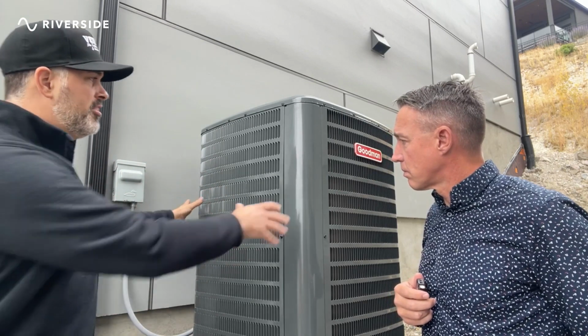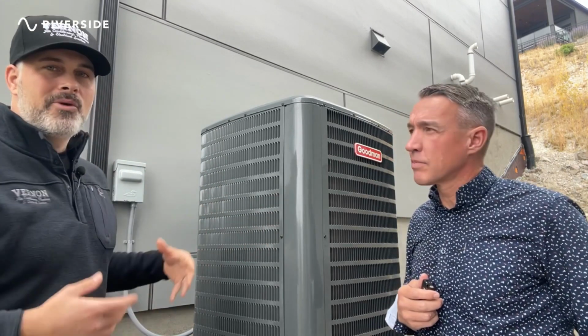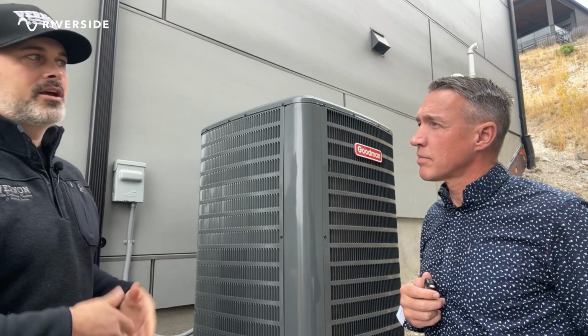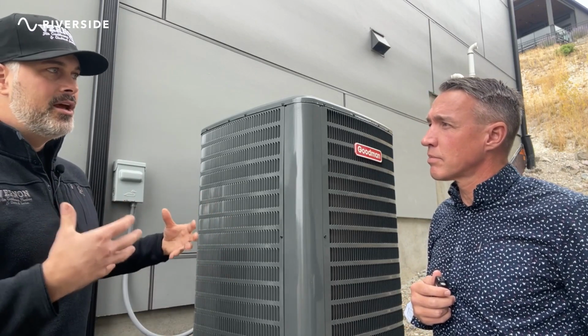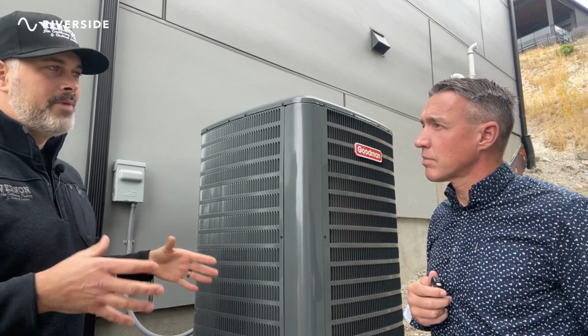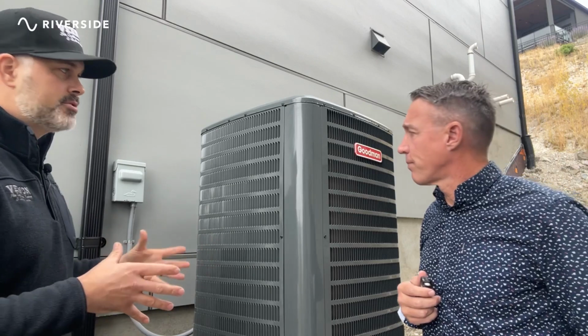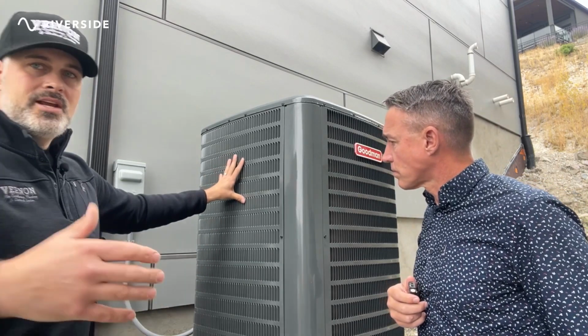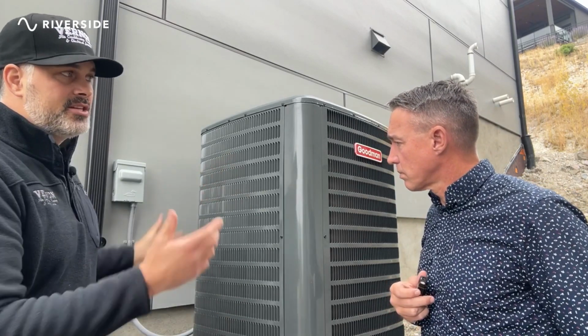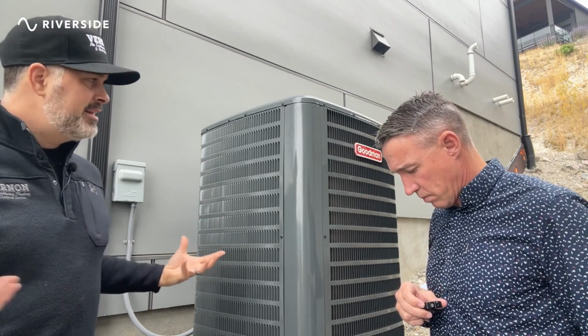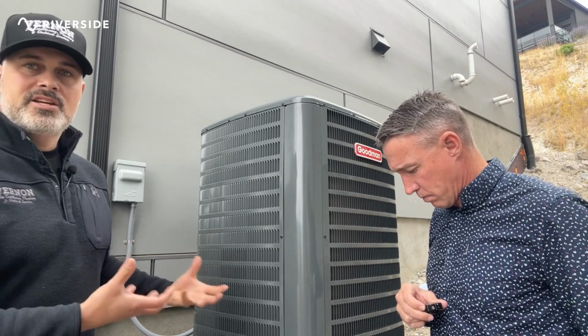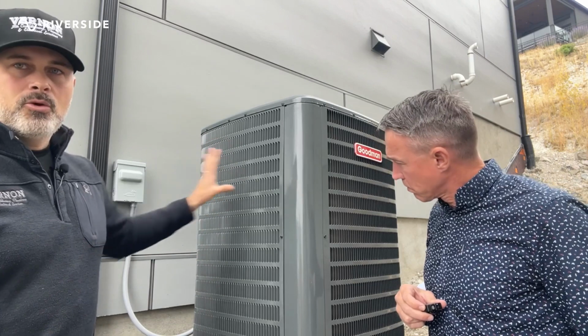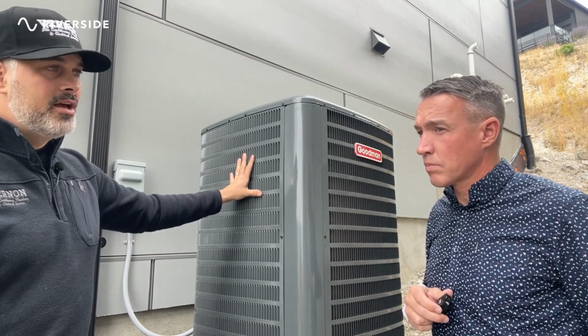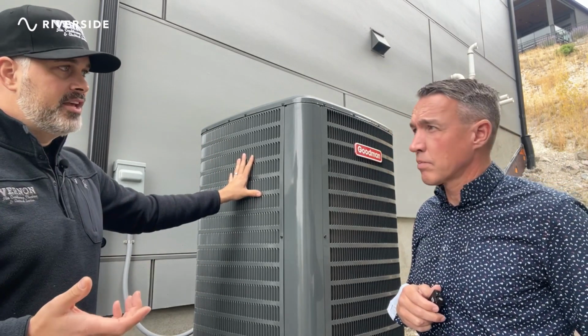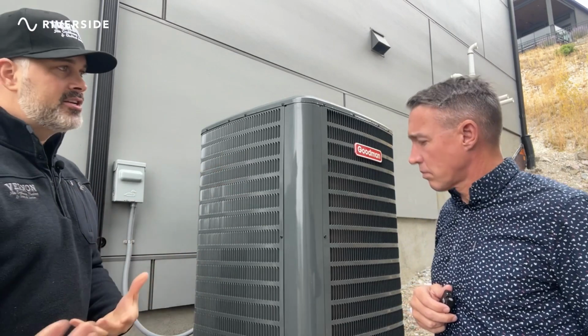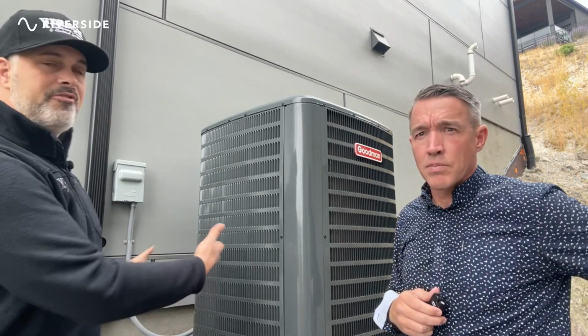In heat pump mode, this absorbs heat, which sounds a little bit crazy. It could be minus 30, it's still absorbing heat. You can actually absorb heat down to about minus 460 degrees. That's absolute zero. But this absorbs heat, and then it travels back in near the furnace to discharge it. Now, from a maintenance standpoint, this is a heat exchanger. So if we can't get airflow across this because it's dirty, it's not going to absorb or get rid of heat, right? Now, on the furnace, you've got the furnace filter, but there's no filter out here.